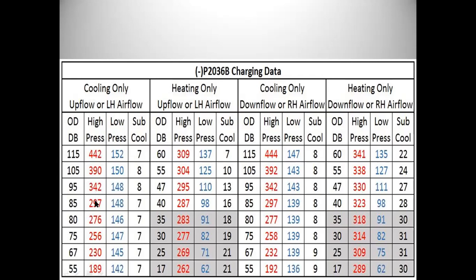So if we'll go over here to the cooling, we'll take an 85-degree day. So 85-degree upflow, our head pressure should be somewhere around 297, suction 148. And if we go over here to cooling downflow, 85, really close again, 297 discharge, 139 on your suction, and it's calling for an 8 on your subcool. So in this case here, I would probably drop that by 3 and go to a 4 subcooling. And on your 8 over here, I would drop that by 3 and put that at a 5, maybe even a 4. And that gives you a nice safe cushion there to not be in the overcharged situation.